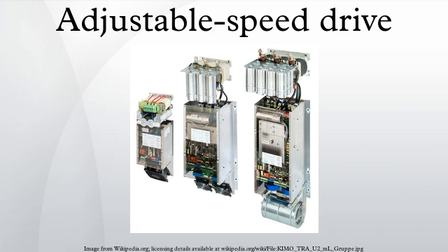Basic electric motor drive alternatives. AC electric motors can be run in fixed-speed operation determined by the number of stator-pole pairs in the motor and the frequency of the alternating current supply. AC motors can be made with one or more stator-pole pairs, the number of which determines the motor's synchronous or asynchronous speed, defined as N = 120F/P, where N is synchronous speed in RPM, F is frequency in Hertz and P is number of poles. The number of such fixed-speed operation speeds is constrained by cost as the number of pole pairs increases.